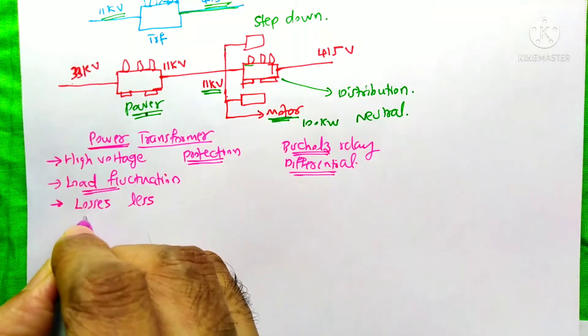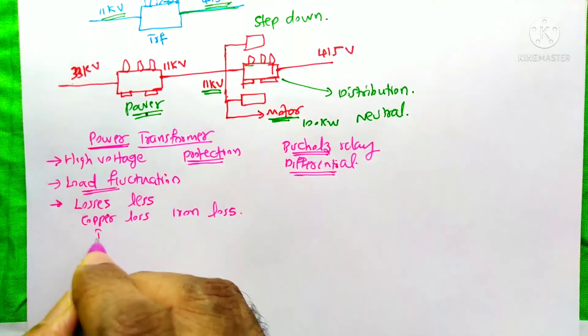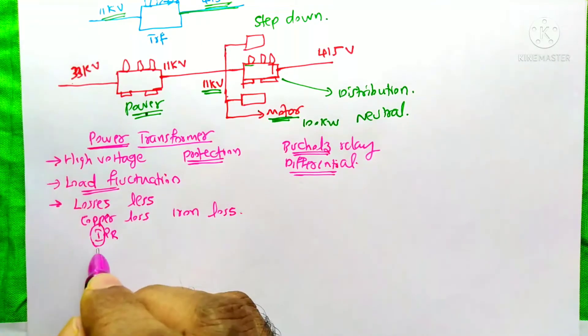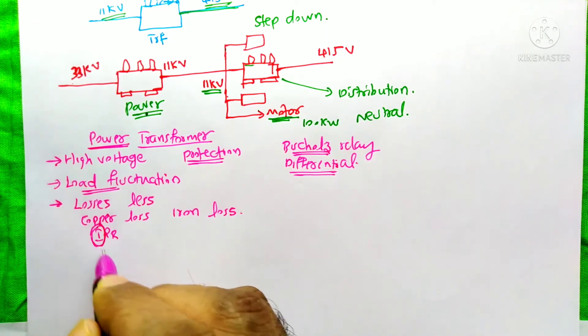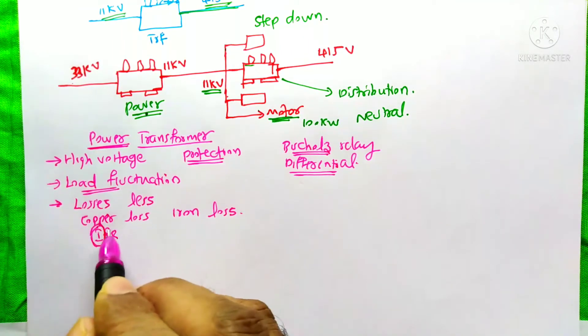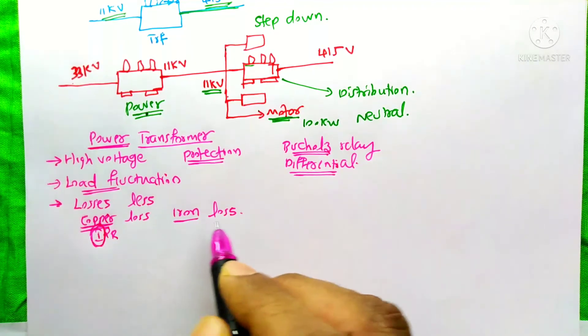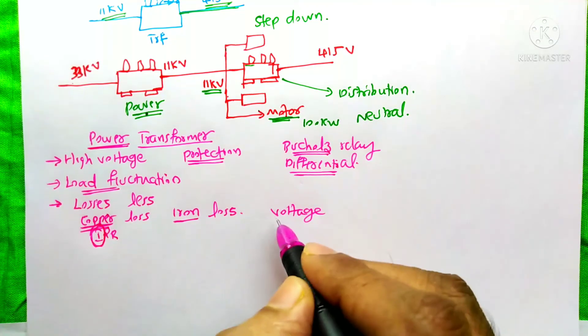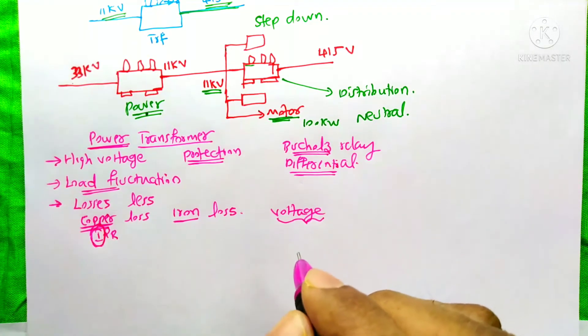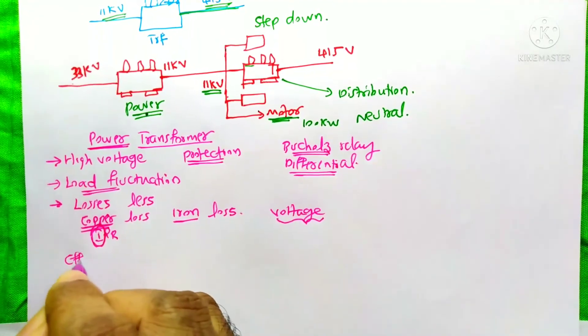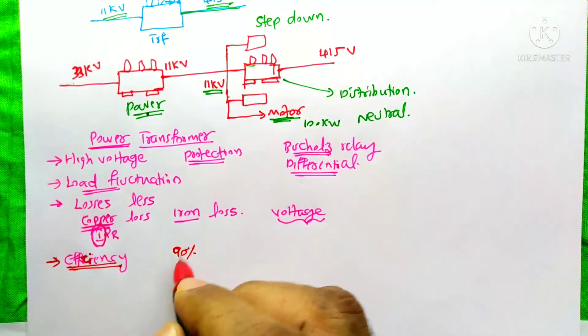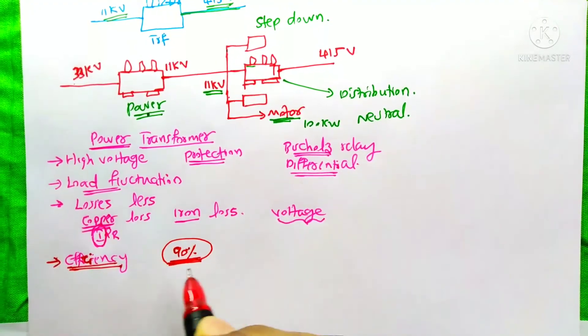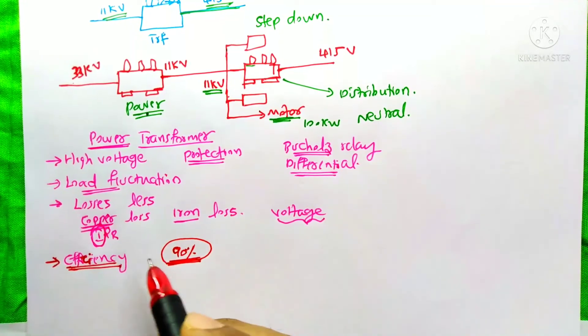The losses are mainly copper losses and iron losses. Copper losses are I²R losses, which mainly depend on current — whenever there is high current fluctuation, there are very high copper losses. Iron losses mainly depend on voltage. Because loads are not connected directly to the power transformer, voltage fluctuation is also very low. Due to these low losses, the efficiency of the power transformer is generally more than 90%.